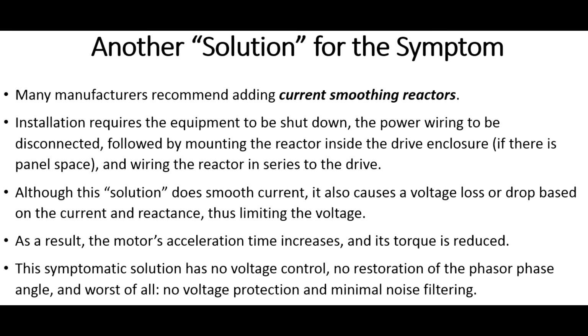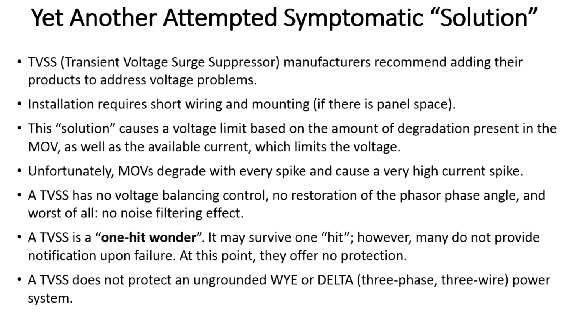They do not address restoring the phase angle differential between phases, and there's no protection from voltage spikes, and it actually does minimal noise filtering. There are various power quality solutions recommended by manufacturers, some of which smooth the current. These particular devices are for limiting voltage.